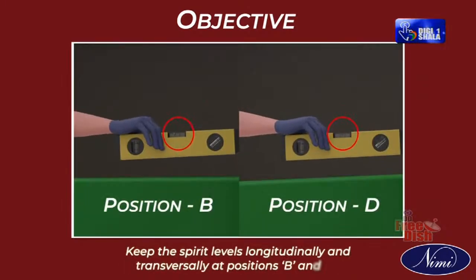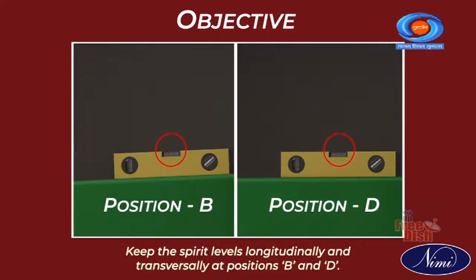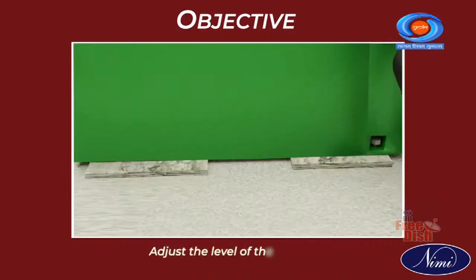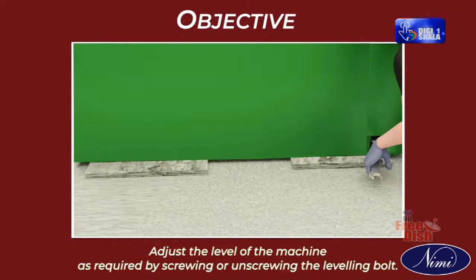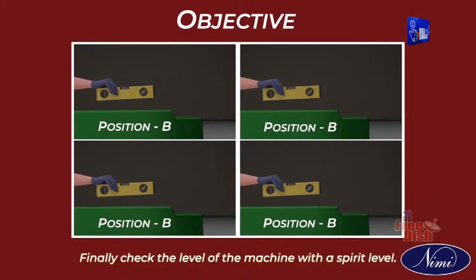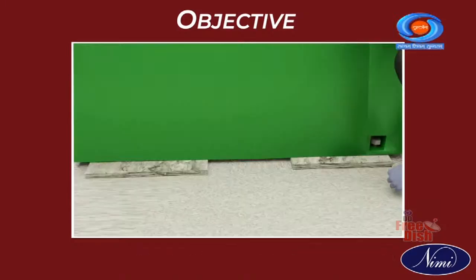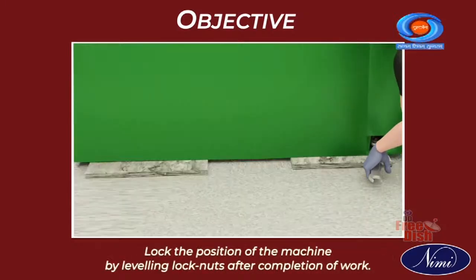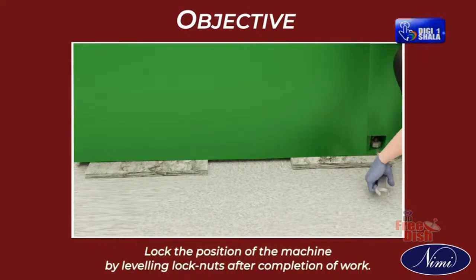Keep the spirit levels longitudinally and transversely at positions B and D. Adjust the level of the machine as required by screwing or unscrewing the leveling bolt. Finally, check the level of the machine with the spirit level. Lock the position of the machine with leveling lock nuts after completion of work.